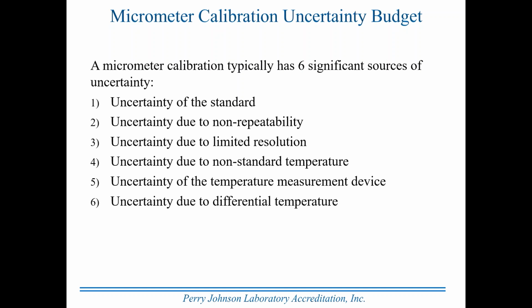So recognizing that the temperature is constantly fluctuating between the acceptable limits and everything in the laboratory is responding to those temperature changes, we can't measure that on an instantaneous basis. So what we do is we make an educated assumption of what it might be. We evaluate the linear coefficient of thermal expansion for the material that the micrometer is made from, the same for the material that the gauge block or whatever we're using as a standard is made from.